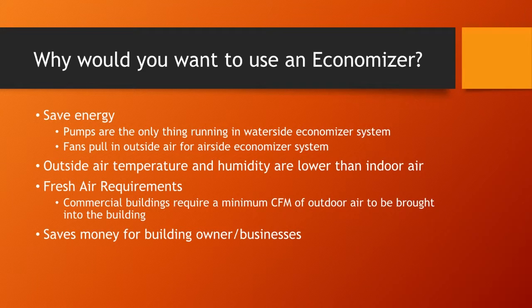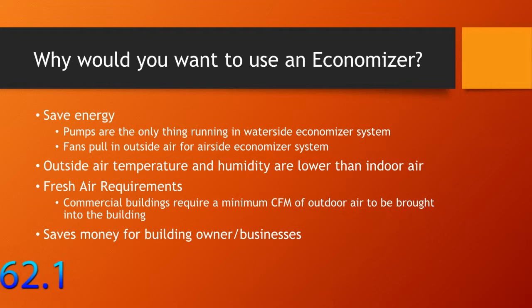Also, fresh air requirements. Commercial buildings are required to have a certain CFM of outdoor air coming in for air exchanges. So if you can just use strictly outdoor air to cool your building, why not? It's just going to be easier. You don't have to worry about that minimum. Just go strictly outdoor only. And it's also going to save money for the building owner and the businesses, and it's also going to give your mechanical systems a break.